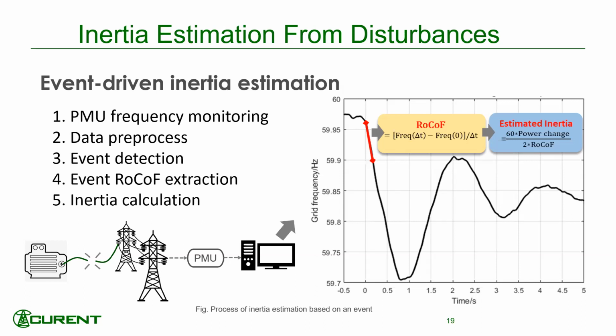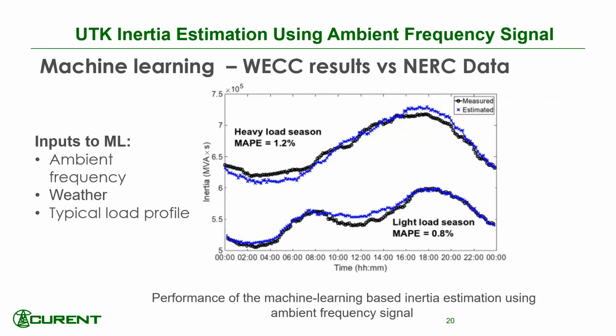But you don't want a system to have this kind of disturbance, so you don't constantly get drops like this. So there are other ways to find inertia, and you can do it with ambient data. If you recall, at different times of the day, the number of oscillations happens differently. That's a way to say that any minor change in the system, load change, topology change, could cause some kind of disturbance and excite the system. Based on that, you can use ambient data to estimate inertia in the grid.